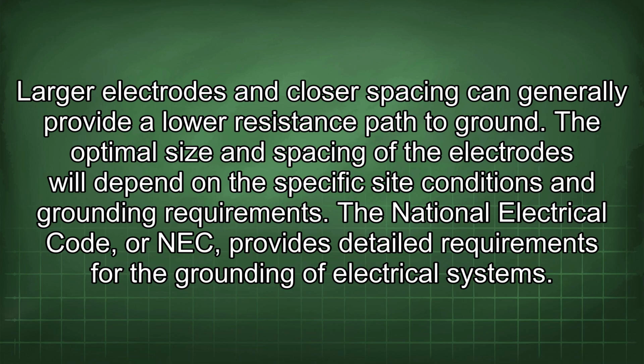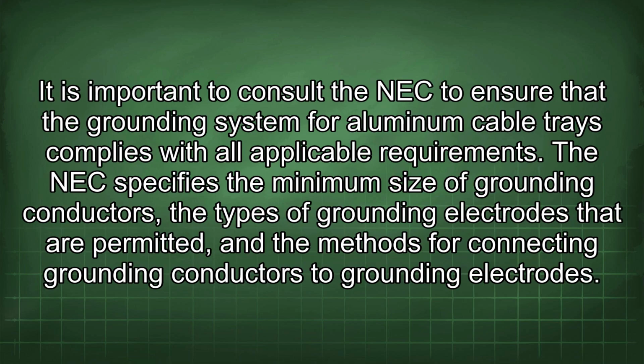The National Electrical Code, or NEC, provides detailed requirements for the grounding of electrical systems. It is important to consult the NEC to ensure that the grounding system for aluminum cable trays complies with all applicable requirements. The NEC specifies the minimum size of grounding conductors, the types of grounding electrodes that are permitted, and the methods for connecting grounding conductors to grounding electrodes.